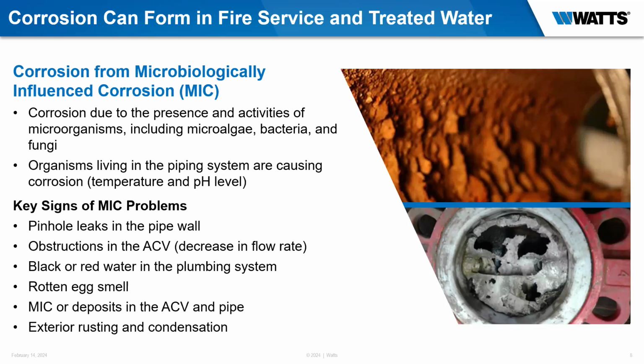MIC really creates an obstruction in the ACV, which decreases its flow rate. So all of a sudden, you may size a 6-inch ACV to give you the amount of fire flow, and it's been sitting there, but it may be decreasing down to 4-inch because of the amount of corrosion building up in that valve. So MIC, or the deposits in ACVs, is critical.